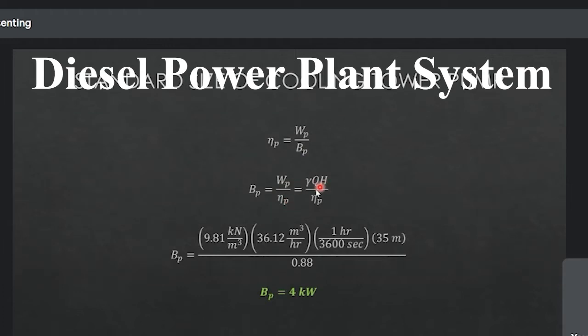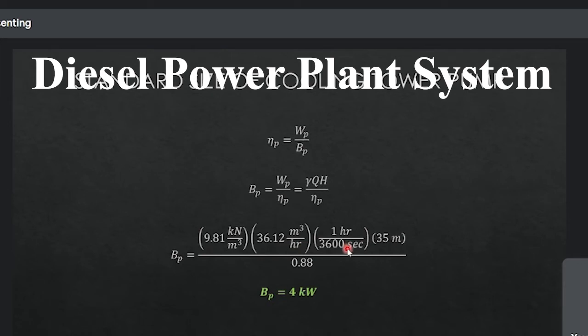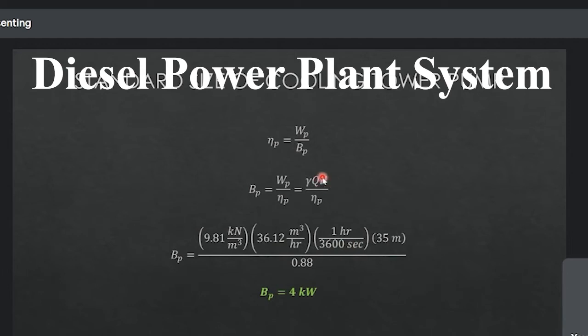Sa fluid machineries natin o fluid mechanics natin, the water power is simply ang gamma QH, o yung specific weight ng water natin, which is given by 9.81 kilonewton per cubic meter. Yung capacity natin, na solve natin kanina, 36.12 cubic meter per hour, kailangan lang natin i-convert into seconds - for every 1 hour, we have 3,600 seconds. Yung total dynamic head natin, which is given kanina doon sa problem, ay 35 meters. Cancel yung cubic meter dito, meron tayong kilonewton at saka meter, that would be kilojoules, divided by second, which would result to kilowatts. Yung brake power natin o yung power na kailangan ng cooling tower pump would be equal to 4 kilowatts.